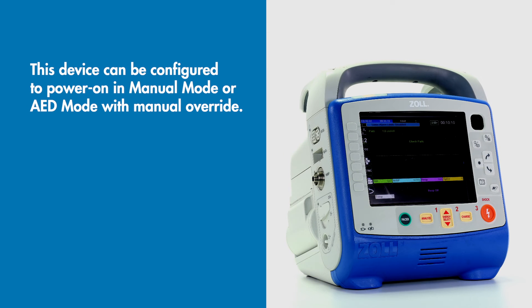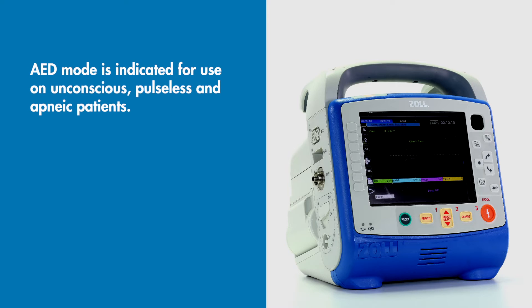This device can be configured to power on in manual mode or AED mode with manual override. AED mode is indicated for use on unconscious, pulseless, and apneic patients.